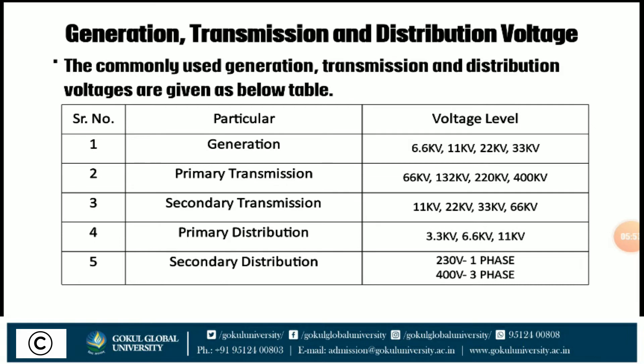Now we discuss about generation, transmission, and distribution voltages. The commonly used voltage levels are: generation voltage is generally 6.6 kV, 11 kV, 22 kV, and 33 kV. Primary transmission voltage is generally 66 kV. Primary distribution voltage is 3.3 kV, 6.6 kV, and 11 kV. Secondary distribution voltage is 230 V for single-phase and 400 V for three-phase.